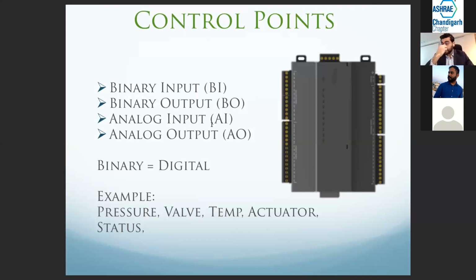Let's take a pump as an example. If a pump is just a simple pump without a VFD, then you have two basic points. One is on and off, which is your binary output, binary because it's 0 and 1, and output because it's going from the controller to the pump. The other is status, where we put a current transducer to tell us if there's current flowing through the coil, and it gives us the signal that it is on or off.